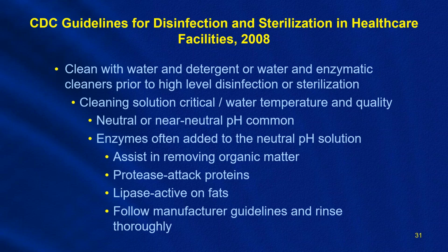Cleaning with water and detergent or water and enzymatic cleaners prior to high-level disinfection and sterilization. The cleaning solution is critical. The water temperature and quality of the water is critical. You want to use neutral or near neutral pH cleaning chemicals. Common cleaners contain enzymes used to assist in removing organic matter. Protease cleaners attack proteins. Lipase cleaners are effective on fats. And you have to follow the manufacturer guidelines and rinse thoroughly with all of these chemicals. There's just so much knowledge and so many different parameters that these central sterile technicians must follow to be effective.